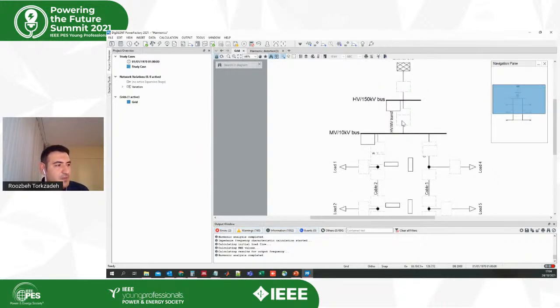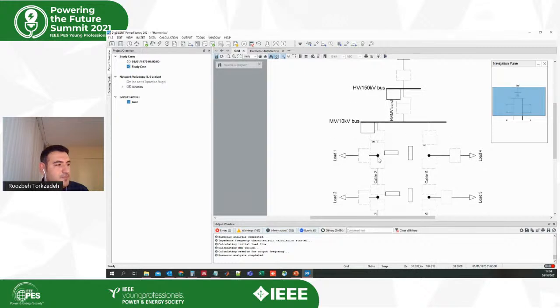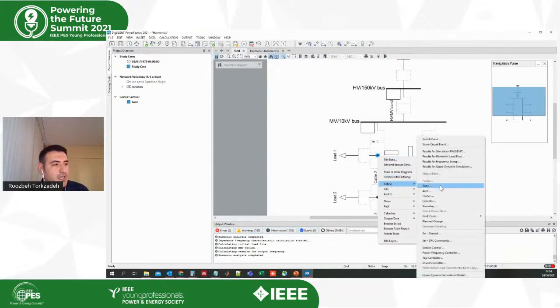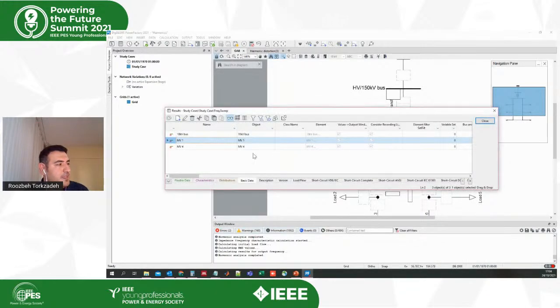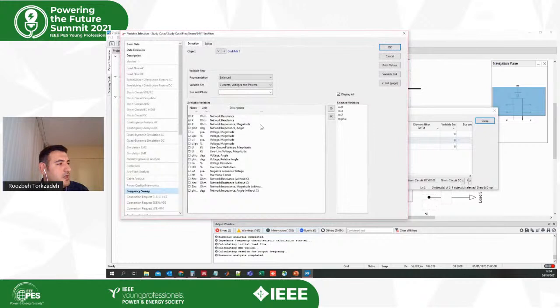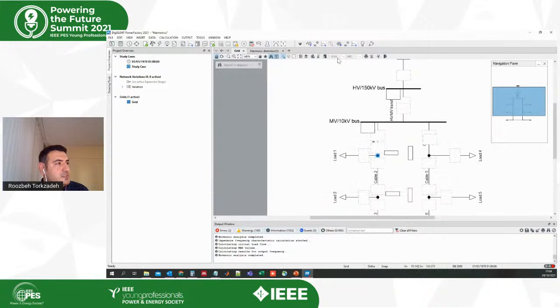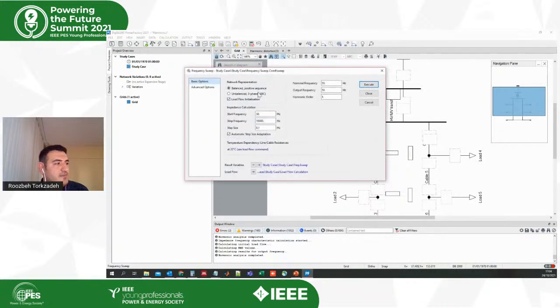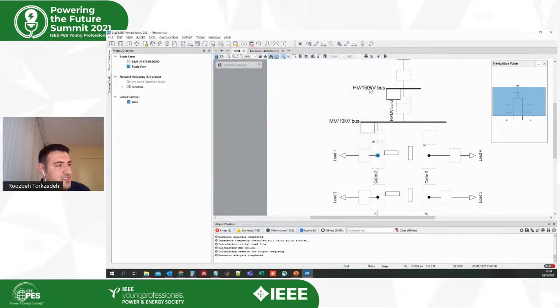For example, I'm going to plot the network impedance characteristic for this node. I right-click on the node, go to the Define tab, then select Result for Frequency Sweep. For this busbar, I'll show the values of the impedance and also the angle of the impedance, then run the calculation again with these two variables using the same settings.